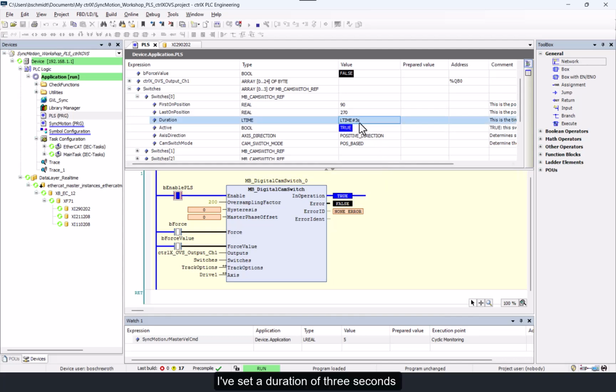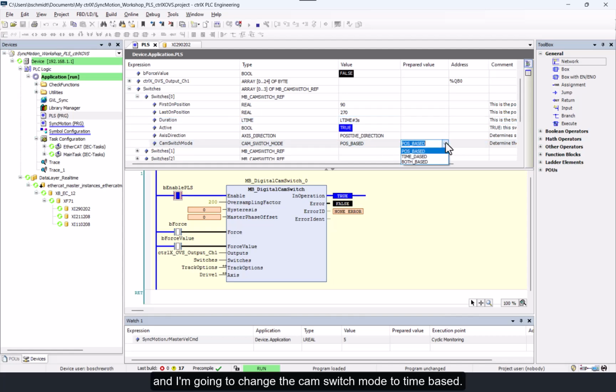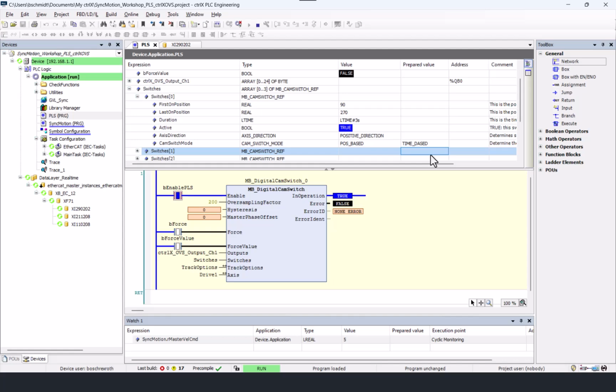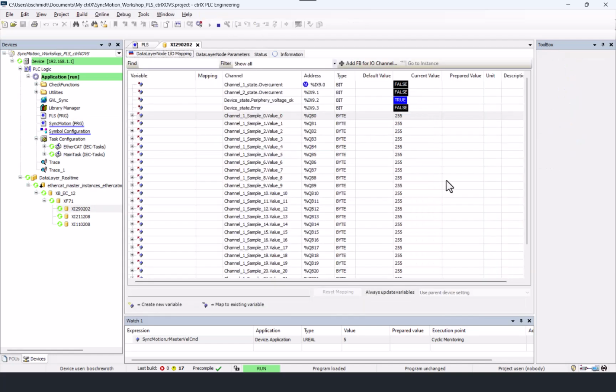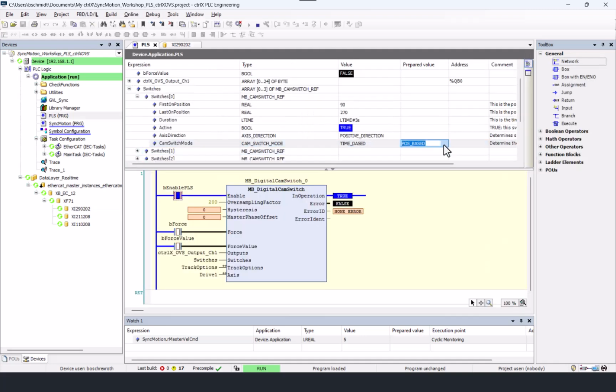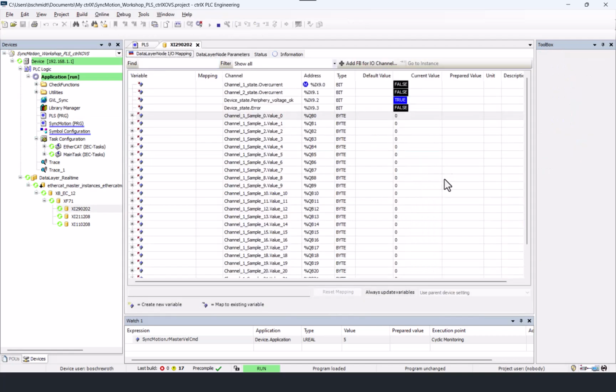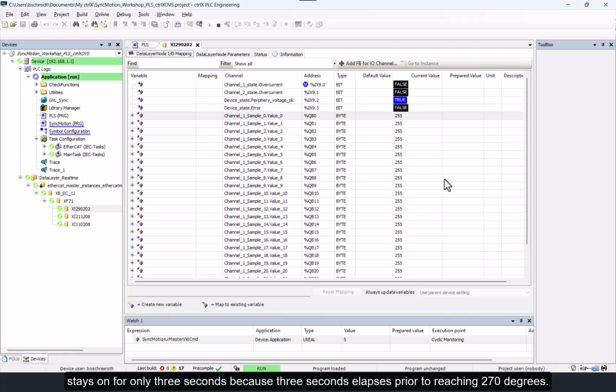I've set a duration of 3 seconds, and I'm going to change the cam switch mode to time-based. And now the output stays on for only 3 seconds. If I switch to both, it still stays on for only 3 seconds because 3 seconds elapses prior to reaching 270 degrees.